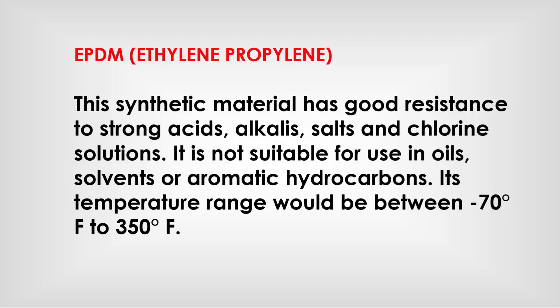EPDM (Ethylene Propylene): this synthetic material has good resistance to strong acids, alkalis, salt, and chlorine solutions. It is not suitable for use in oils, solvents, or aromatic hydrocarbons. Its temperature range is between -70°F to 350°F.